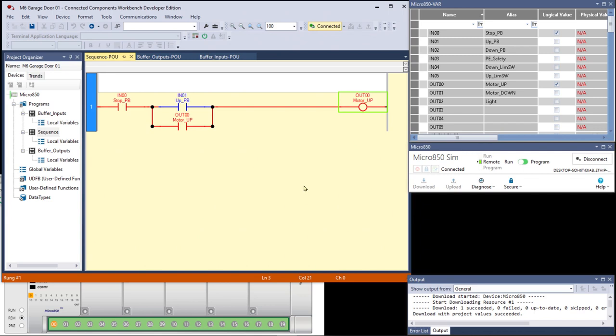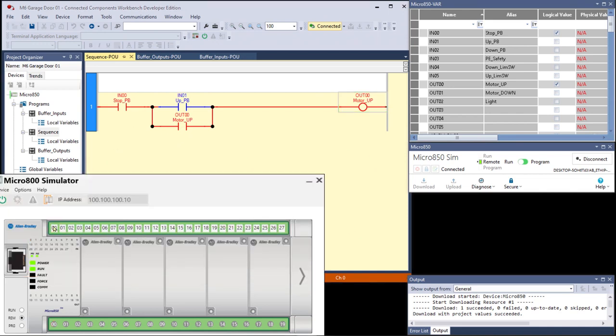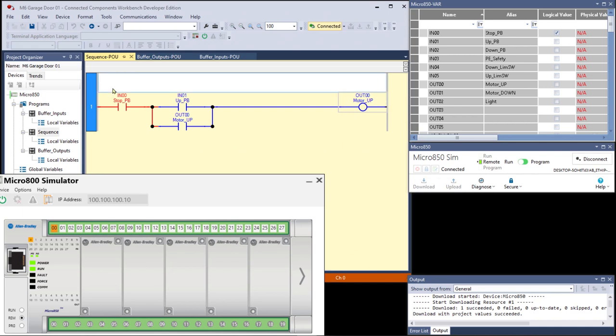With your rung in the above state that would be what you see right here and without using the switches connected to the IO terminals that would be zero and one. Can you think of another means to energize the memory location output zero? Yes. Now I can go here toggle and it's on. If this gets on then this is going to be true and it's going to stay on. I can do the same thing. I can toggle it here too. It doesn't matter which one I toggle it's going to have the same thing because I'm not toggling the logic here. When you right click on this stuff and toggle you're not toggling the logic or the instruction you're toggling the bit in memory. So whether I do it here or over here if I right click and toggle I'm toggling OUT00 in memory not this instruction. Did it matter which instruction you chose to toggle? Nope. This is the classic momentary start stop rung of logic. Do you think that it would matter what order we put in the start and the stop instruction? No.